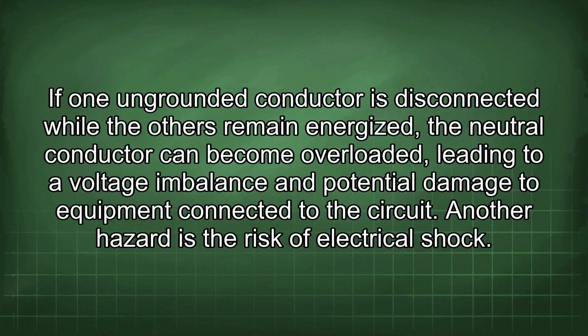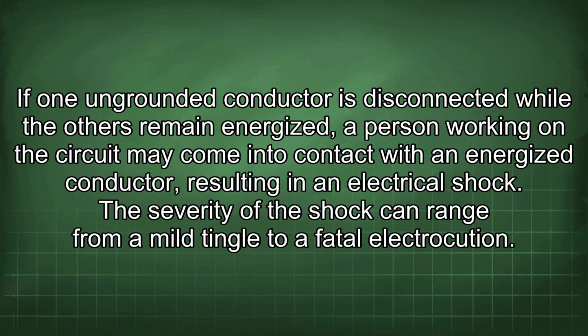Another hazard is the risk of electrical shock. If one ungrounded conductor is disconnected while the others remain energized, a person working on the circuit may come into contact with an energized conductor, resulting in an electrical shock. The severity of the shock can range from a mild tingle to a fatal electrocution.